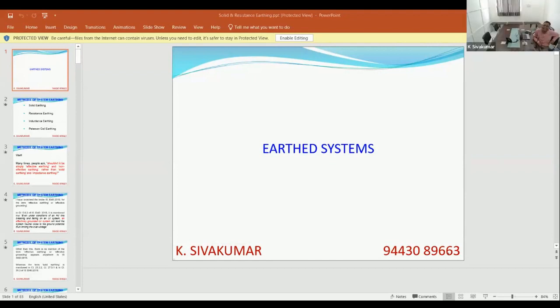If it is LV, data center is LV. LV is solidly earthed only. Please remove any myth you have that you can escape by providing any reactance earthing so that you can limit harmonic currents. No. If you are talking of LV supply in the data center, it must be solidly earthed only. Yes, if you are apprehensive of harmonic current, triplen harmonic currents, you provide 200% neutral. That is the latest practice.